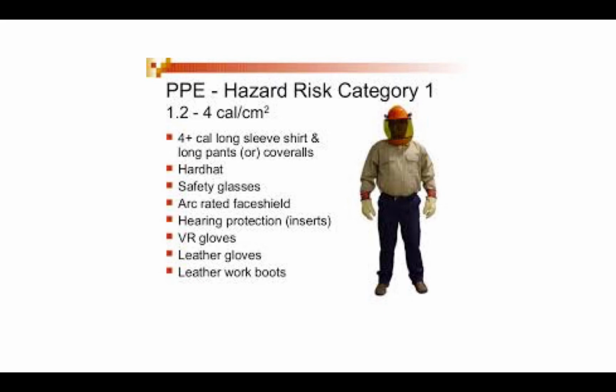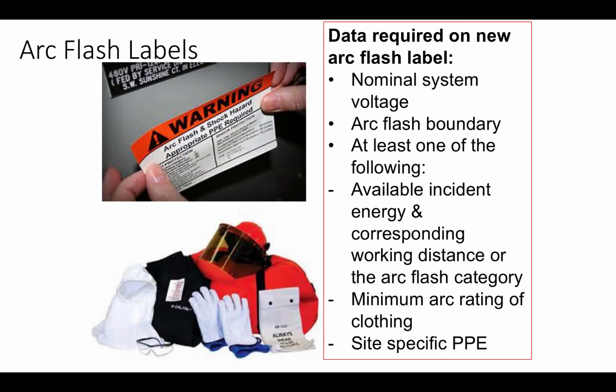The minimum PPE requirement is hazard risk category 1. You must have a long sleeve shirt and long pants or coveralls. You must have a hard hat on. You have to have safety glasses on. You have to have an arc rated face shield. You have to have hearing protection. Those are the little foam inserts for your ears. You have to have gloves, with leather gloves over them, and leather work boots. In other words, you cannot have any exposed skin when you're dealing in arc flash category 1.